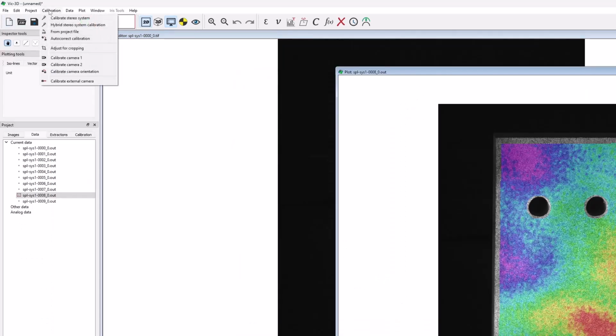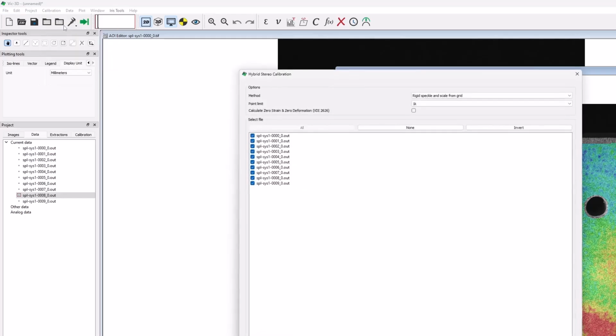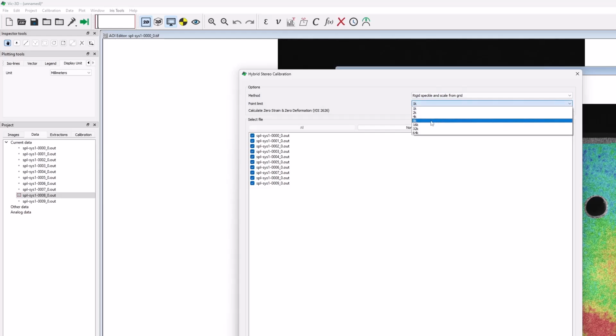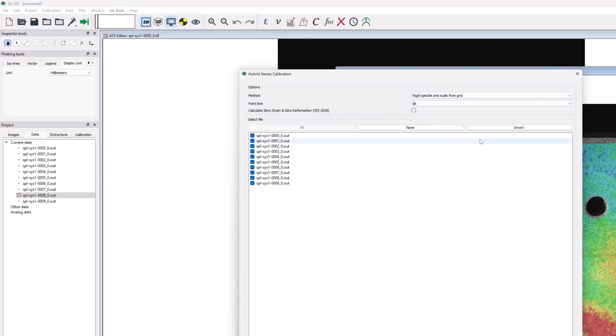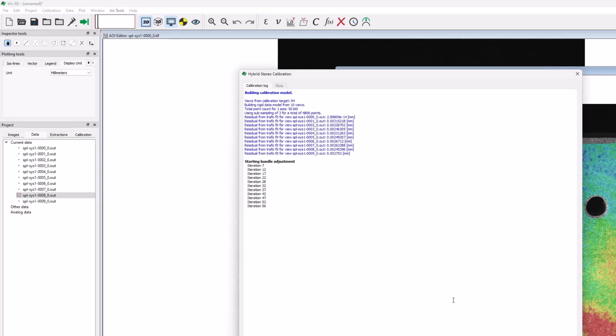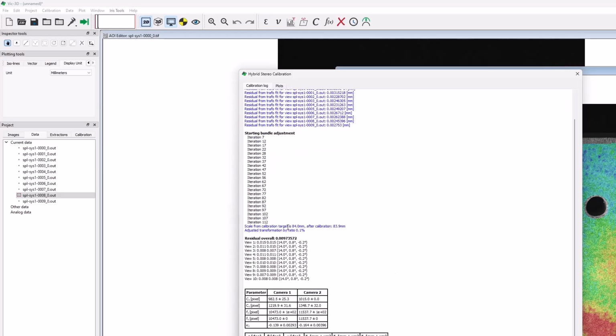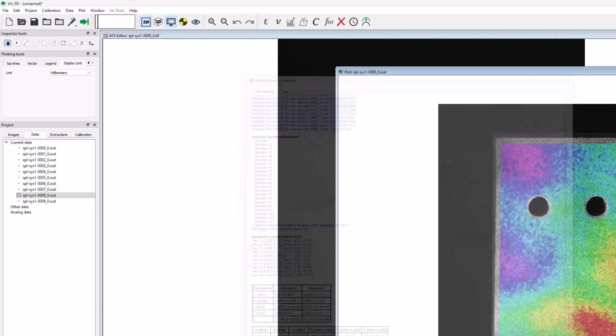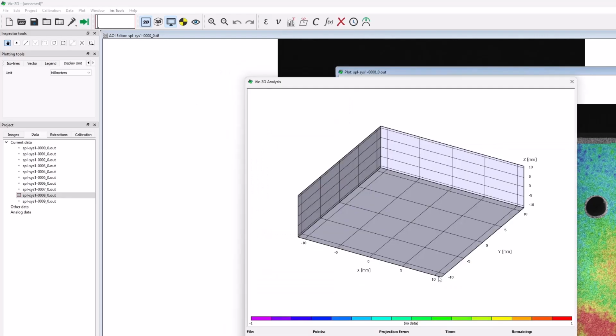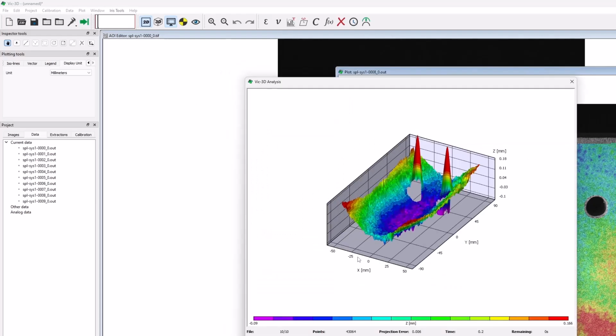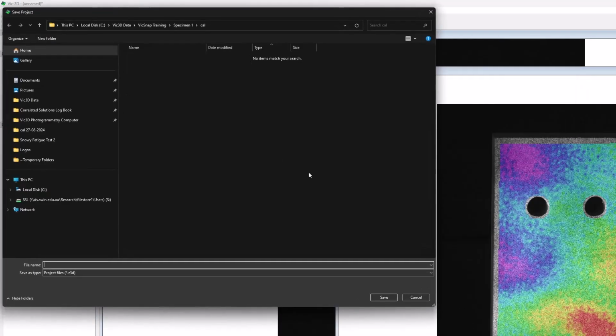Go to Calibration, Hybrid Stereo System Calibration. Set the point limit to 4K or 8K, doesn't really matter, and then run this. This improves the calibration by utilising the specimen calculations within the calibration. Recalculate the specimen again, and you'll notice that the projection error has reduced significantly. Accept the cal, then save the project. Name it as a calibration project and close VIC 3D. And that's method 1, which will be perfectly adequate for 90% of work.